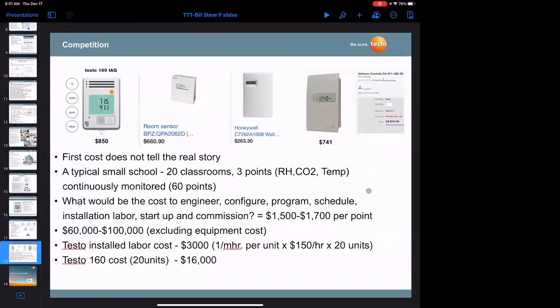So what I did here was take a couple of examples. I went online and looked at currently available products from Siemens, Honeywell, and Johnson Controls. Both Siemens and Johnson Controls have units that measure temperature, relative humidity, and CO2. Honeywell has a unit that does humidity and temperature, or CO2 and temperature, but not all three, so you'd need a second module. These prices are current internet pricing compared to our current street retail list price, so we're very competitively priced against these guys. The important thing is I took 20 classrooms, knowing we need to monitor these three variables.